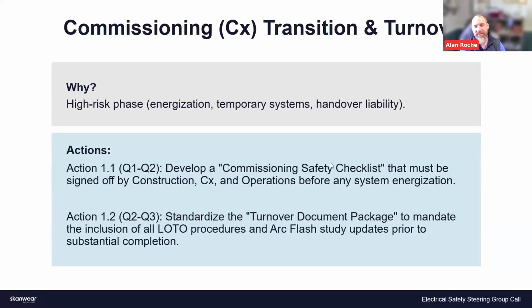So it's definitely about looking at your owner requirements. Different owners have different QA/QC requirements around electrical safety, whether that's QA/QC meetings or what's required for pre-energization inspection. That pre-energization inspection is becoming more and more critical, because it's your last stop to prevent an arc flash. We talked about that at the conference—how many people have seen arc flashes upon initial energization?